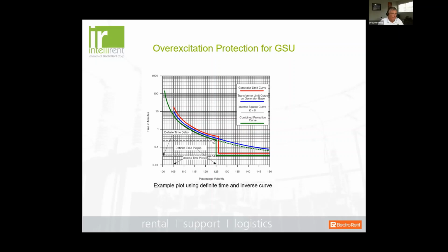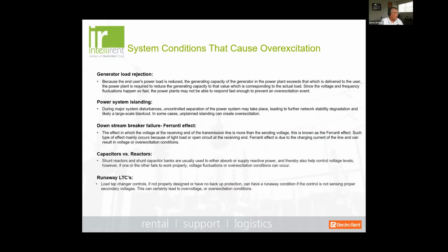Okay, so overexcitation can happen for a number of different reasons, but we usually enable this protection on a GSU because it has to do with a faulty AVR, or voltage regulator, or excitation system. Now, it's also important to know that if you get into high voltage situations, system conditions can cause overexcitation as well: generator load rejection, power system islanding, Ferranti effect from breaker failure downstream, capacitors and reactors that should be either on or off but are in the opposite state, or runaway load tap changer controls.